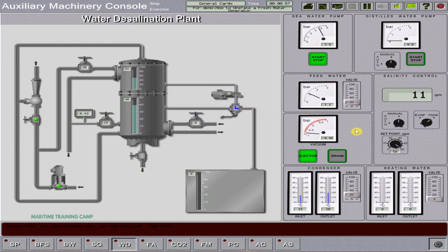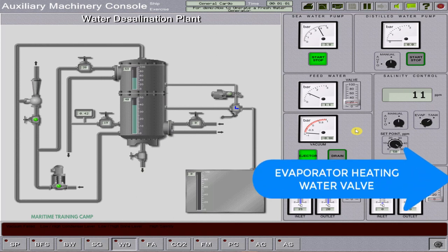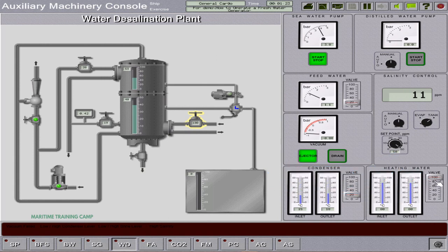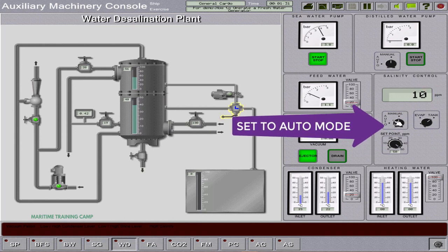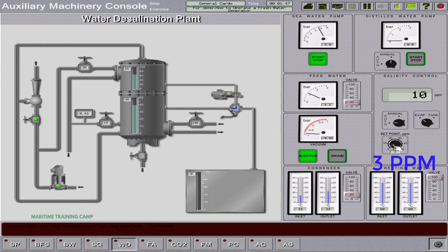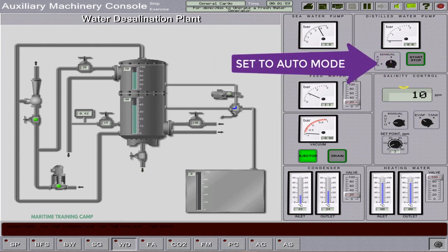After that, we proceed to open the evaporator heating water valve, as appropriate for the heating water temperature and the desired plant capacity. We open this heating water valve at 100%. We then set the solenoid control valve switch on the salinity control group to auto mode, and adjust the set point of the distillate salinity control to the required position — in this case, around 3 ppm for production of boiler water. After that, we set the distillate water pump control switch to auto mode.